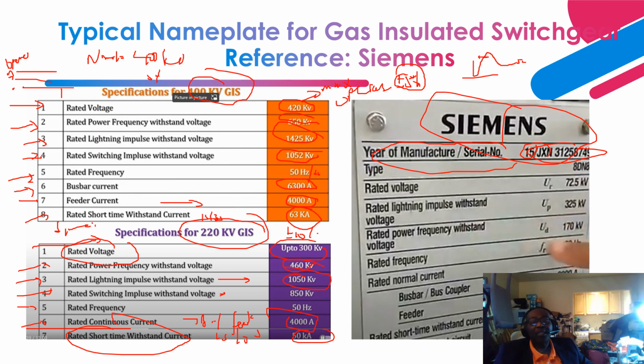So anytime you want any information on this GIS, this is the serial number that you need to contact the manufacturer. Once the manufacturer plugs in this serial number, it provides everything: all the engineering documents, all the simulation studies, all the design documents, all the one-line and three-line diagrams, the factory acceptance testing, and all the in-stage manufacturing quality testing that was done on this GIS will come up. So that is how manufacturers utilize the serial number to access every piece of information. Anytime you want to contact your manufacturer, utilize the serial number.